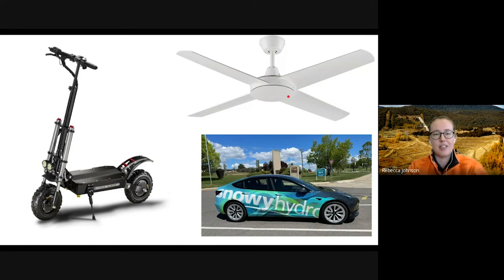But at Snowy, we have a few different applications, and one of them is called dynamic braking. This has to do with the generator and turbine that we've been talking about this whole session. Dynamic braking slows down the unit by converting the rotational energy into heat by electrical means. So you use the motor effect to slow down the unit instead of using traditional friction brakes like you find in your car or your push bike, where the disc physically attaches to the rotating object to slow it down.